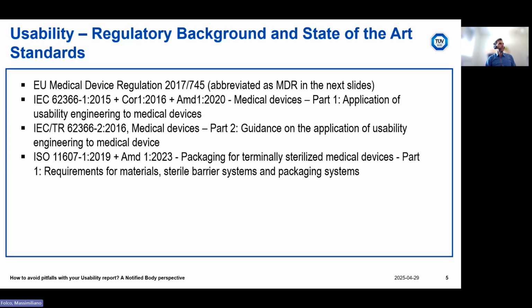Then regarding the state-of-the-art standards, for sure we have IEC 62366-1, released in 2015, then corrected and amended in the following years, regarding the application of usability engineering to medical devices. There is a guidance to this standard, so the part 2 of 62366, released in 2016. And then I also included ISO 11607-1 2019, related to the materials, sterile barrier systems and packaging system for non-active medical devices, because I have a slide related to the usability evaluation for aseptic presentation that is required by this standard.